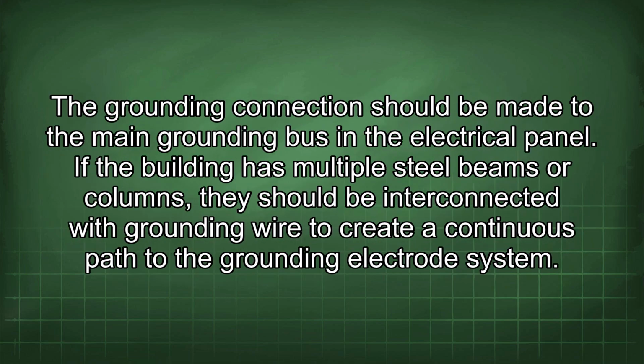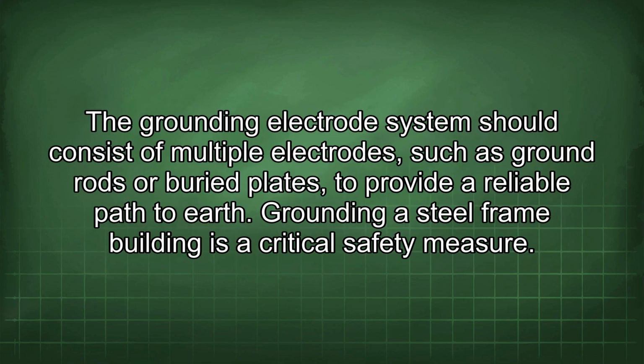The grounding connection should be made to the main grounding bus in the electrical panel. If the building has multiple steel beams or columns, they should be interconnected with grounding wire to create a continuous path to the grounding electrode system. The grounding electrode system should consist of multiple electrodes, such as ground rods or buried plates, to provide a reliable path to earth. Grounding a steel frame building is a critical safety measure.